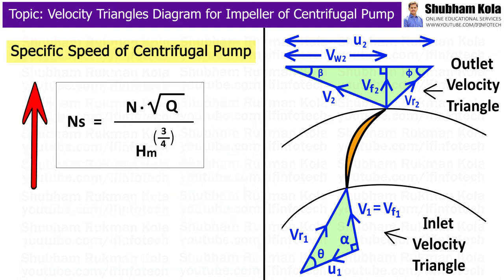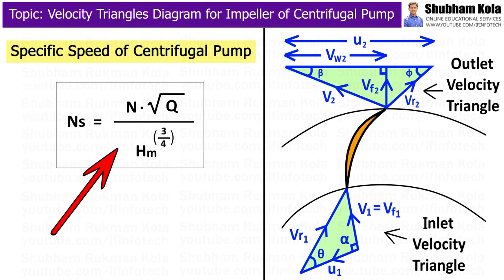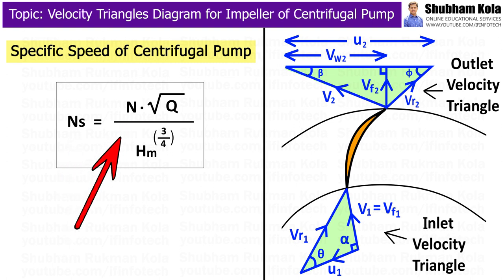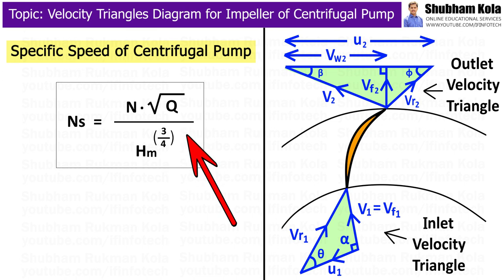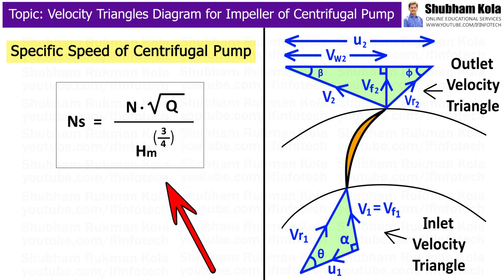The specific speed of a centrifugal pump is given by the formula: Ns = N × √Q / Hm^(3/4), where N is the rotational speed of the impeller, Q is the discharge rate, and Hm is the manometric head.